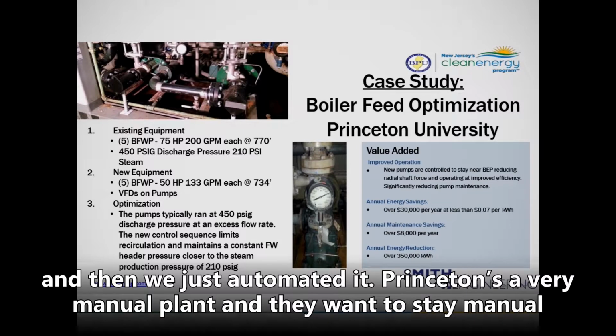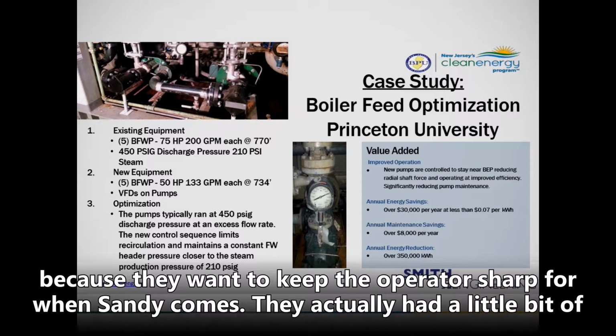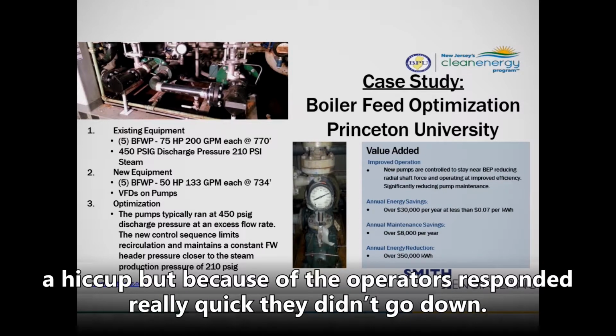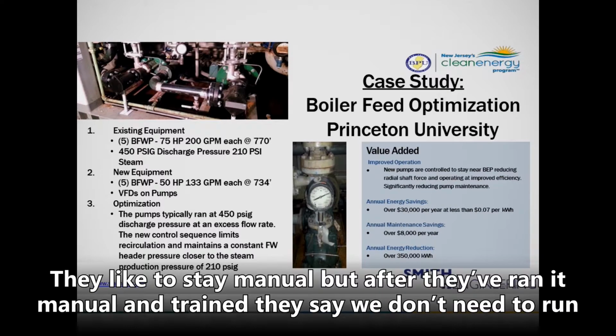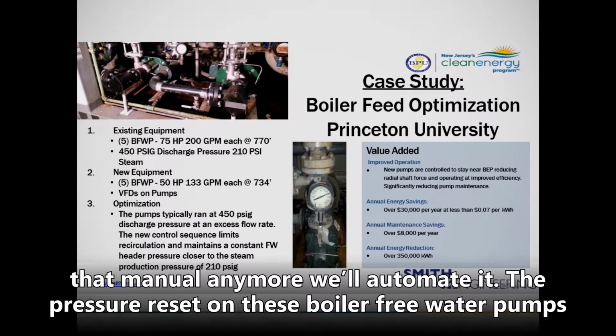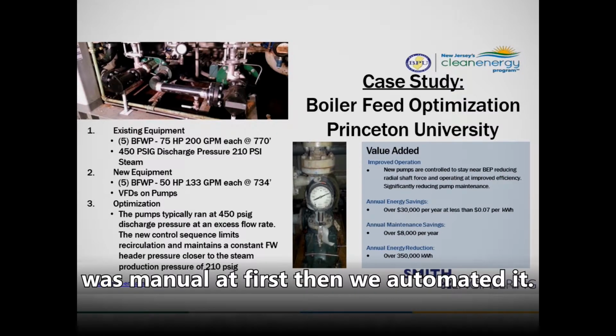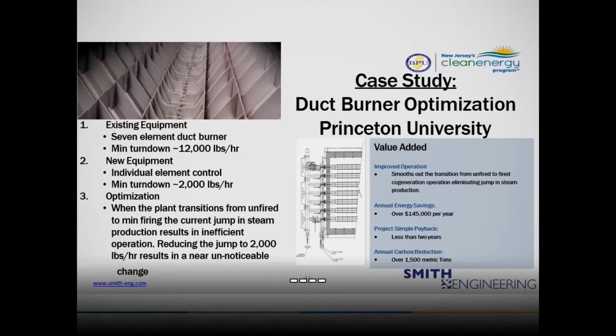Princeton's a very manual plant, and they want to stay manual because they want to keep the operators sharp for when Sandy comes. They actually had a little bit of a hiccup, but because the operators responded really quick, they didn't go down. So they like to stay manual, but after they've run it in manual and they've trained, they said, okay, we don't need to run that in manual anymore, we'll automate. And so the pressure reset on these boiler feed water pumps was manual at first, and then we automated it.